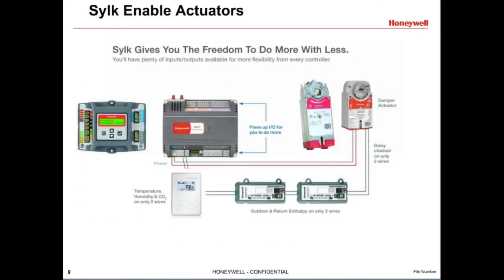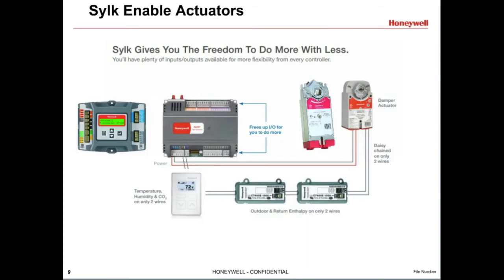Sylk is Honeywell's communicating bus. Sylk spring return actuators are compatible with any Sylk-enabled controllers, such as Jade economizers and Spyder controllers. Sylk is a two-wire polarity-insensitive bus for communication between a Sylk-enabled controller and a Sylk-enabled actuator, and other devices like sensors. With Sylk Bus, you can daisy-chain Sylk devices. This frees up input-output points on the controller. The bus sends feedback from the actuator that helps with early fault detection and diagnostics. This includes actuator cycle count. If the actuator is stalled, it even measures peak VA to warn of potential equipment issues.